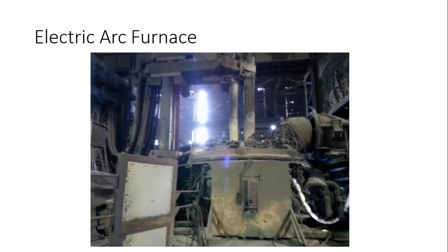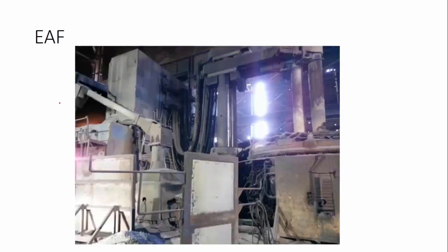Now, these huge cables, which you can see in here, are the main feeding source for the graphite electrodes. These are water-cooled cables, which have to be water-cooled because they carry huge currents and therefore get very hot, and if it were not for the water cooling, they would melt. Now, behind this wall is the furnace transformer, which is a huge transformer, and we'll see it in a little while. Here you can see a little better the detail of the vault that contains the transformer. The transformer is in here. These are the cables that go from the transformer to the furnace. So this is a quite recent furnace. I think it's 6 or 7 years old.